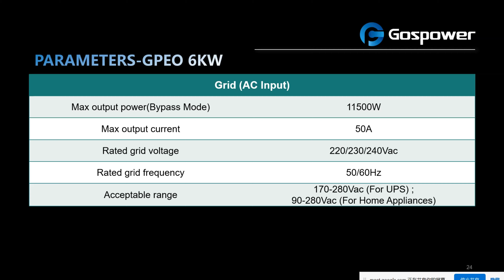In the AC grid input part, the maximum output power under bypass mode is 11,500 watt, and the max output current is 50 amps. On the battery side, this inverter supports LiFePO4 lithium batteries and lead-acid batteries. The maximum charging current is 120 amps, and the maximum discharge current is 130 amps. We also use RS485 for the BMS communication.